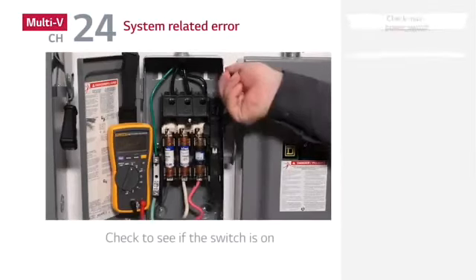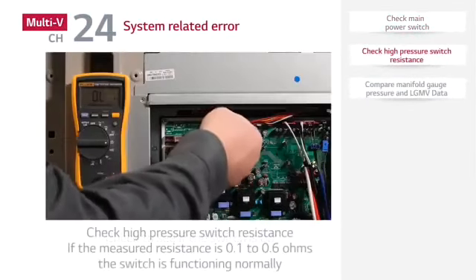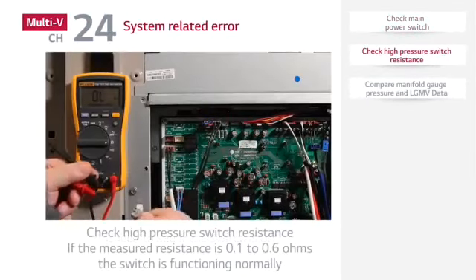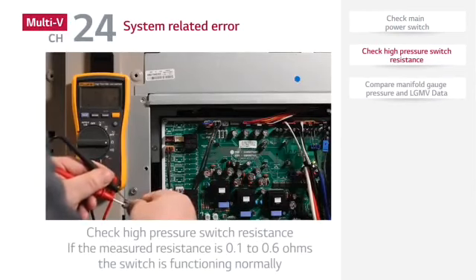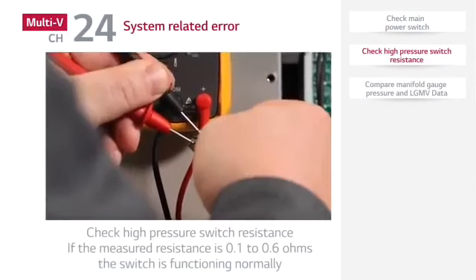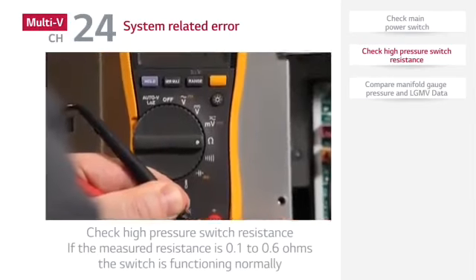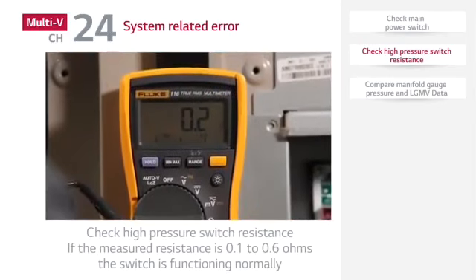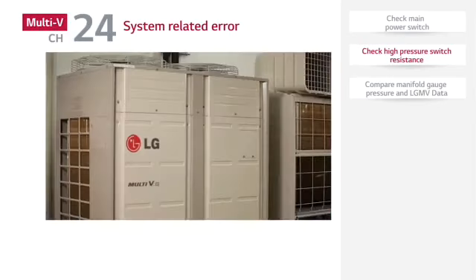First, check the power. Next, check the high pressure switch resistance, and if the measured resistance is 0.1 to 0.6 ohms, the switch is functioning normally. Be sure to check the area around the outdoor unit to ensure that there are no environmental factors such as dirty coils, obstructed fans, etc.